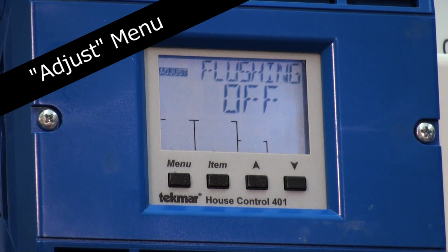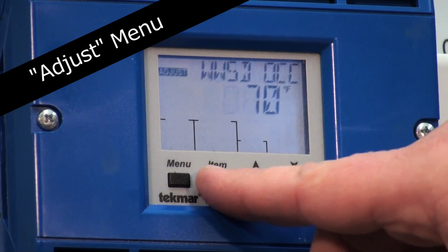Flushing is off. Flushing pertains to a different type of system. If you were putting this on and using a water heater to do radiant floor, you turn flushing on, it will actually run each heating zone at least one time a day to stop stagnant water from happening.